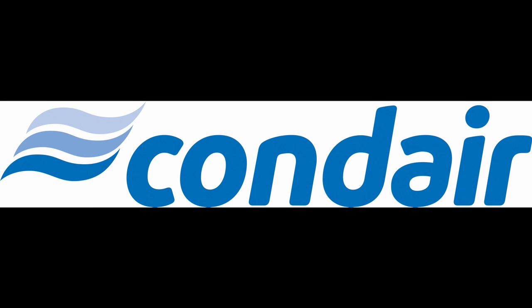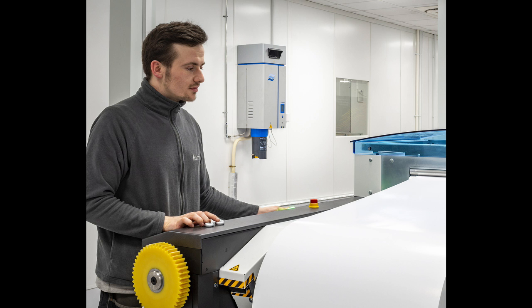Dave Marshall George, sales director at Condair, says humidity must be controlled in the printing industry for the best quality results. The Condair RS is a popular choice for digital print rooms as it offers very accurate humidity control and has an innovative scale management system. When scale forms on the heating elements, as it will do in any steam humidifier, it breaks off and falls into a scale collector tank located at the bottom of the unit. This tank can easily be emptied, enabling the scale to be removed from the system without the need for professional servicing.